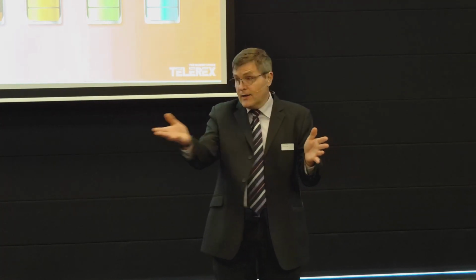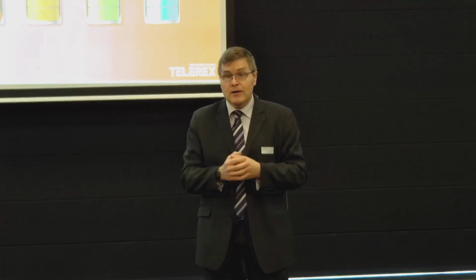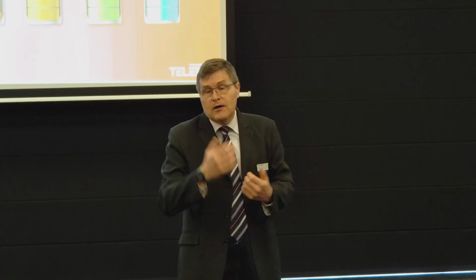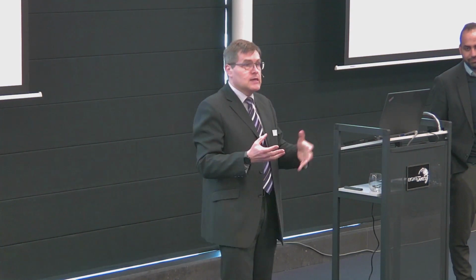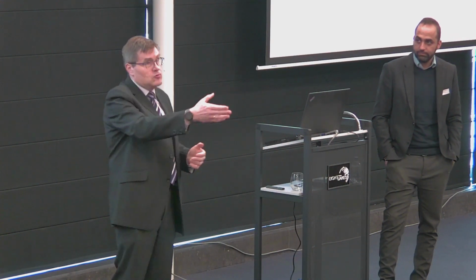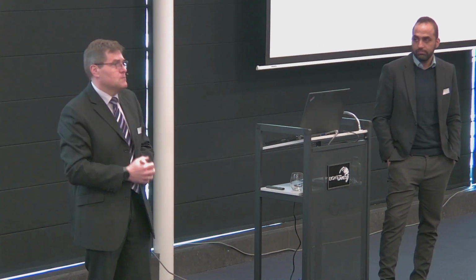And after, I need to give to all my customers which are connected to my network the pollution that they can emit in my network. So if I allow you 6% and my target is 6%, that means that you have 0, because everything is taken by the first customer. So then we have what we call the planning level. And so we arrive to, I would say, you can pollute to 5% THDI or THDV, and you 4.5%, and altogether we will respect the limit.